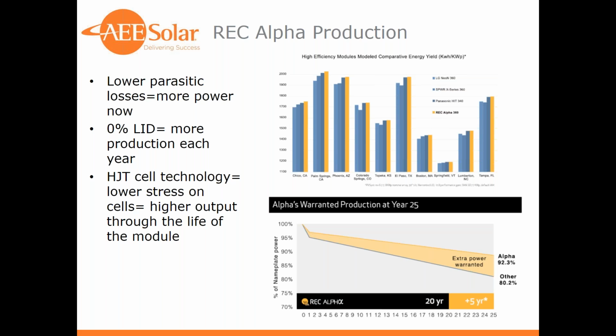But really, the difference between those small differences over the life of 25 years add up to some really significant production. So it's the difference between getting 92% of a 365 watt module at year 25 versus only 80%. So what's 12% on a 365 watt module? It's about 40 or 50 watts. If you could say at 25 years this is going to be a 330 versus a 280, that's a huge difference. Think about what you would pay for a 280 now versus a 330. So really some profound improvements here on production and yield, and again, they're backing it up with warranty.